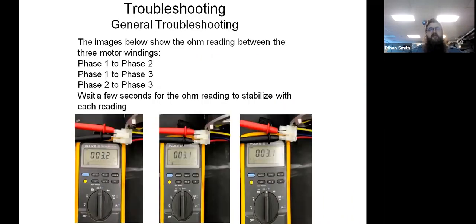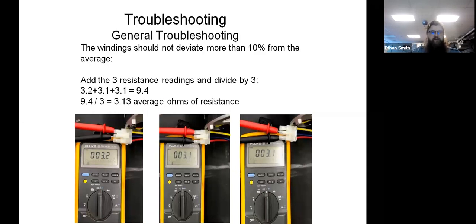Okay. The other thing you need to do is check resistance between all 3 legs of the motor. This is a 3-phase motor. They should all be pretty close to equal. In fact, we want those to be no more than 10% different from each other. So we have 3 of them here. We got 3.2, 3.1, 3.1. You can add those together: 9.4, divide by 3. That's our average ohms of resistance. As long as these 3 resistance levels fall within 10% of that average, our motor is okay. So these are obviously all within 10%, because 10% would be 0.3, and we're all within 0.1 of that average. So this motor is okay.